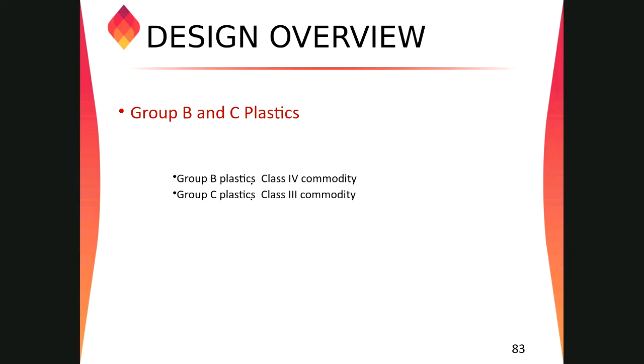So for facilities like that, the best option is that you protect that area with the highest hazard, keeping in your mind which will be the highest hazard group for this case. So it will be considered as group A only. Yeah, consider the group A plastic. This is the first option. There are different options for that one. There are 4 or 5 options. The best one is to consider the highest hazard to avoid any kind of problem in the future, right?